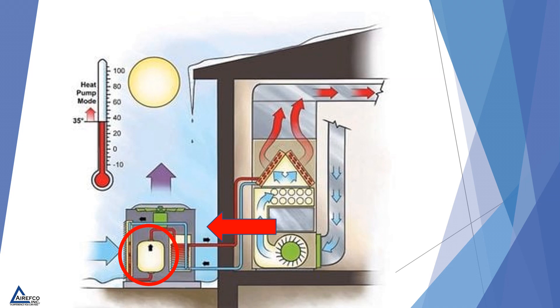Therefore, the refrigerant will seek the coolness of the compressor to reside, and when the compressor starts up again, we may have liquid refrigerant present in the compressor that could cause real damage. This is why we want crankcase heat available, so we can keep the compressor warm and keep the refrigerant from migrating to the compressor in the off cycle.